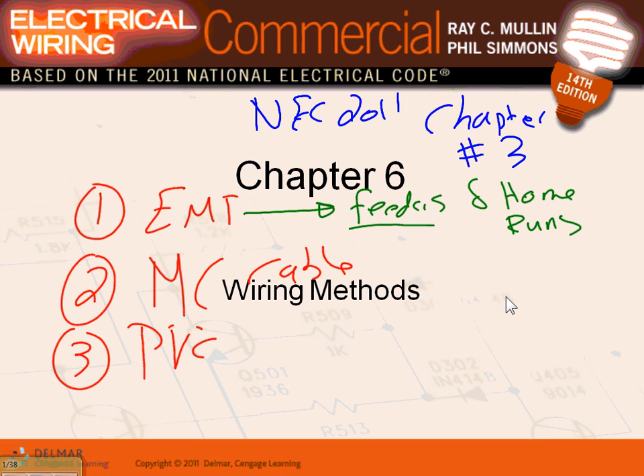So if you need your friend Chad's advice, when you do EMT, always focus on EMT for the home runs for branch circuits, as well as the feeders. What's a feeder? All the feeders that we talked about in your project, guys, the 100 amp and the 200 amp panels, all of them, what did we say we're going to use? EMT. For branch circuits, at least the home run branch circuit, the home run from the first J box in the ceiling all the way to the panel, it's a very good idea to use an EMT conduit.